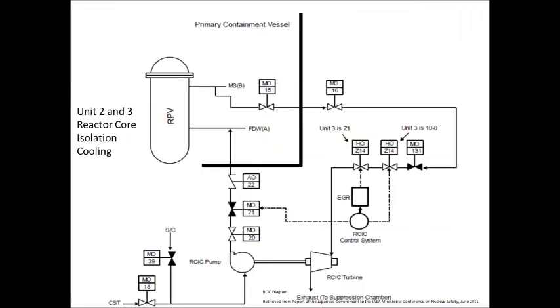The purpose of the reactor core isolation cooling system is to remove decay heat and supply makeup water to the reactor pressure vessel when isolated from the turbine condenser. Primary steam is bled off the reactor through motor and hydraulically operated valves to the RCIC turbine. This steam drives the turbine and is exhausted to the suppression chamber within the wet well.